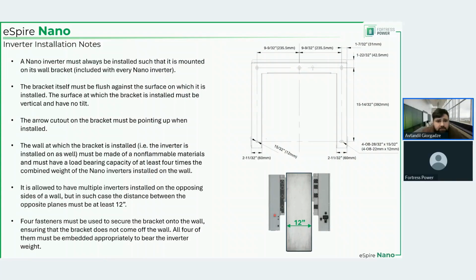The wall which you use to mount the inverter must be non-flammable. That is addressed by default when we're talking about the battery cabinet because it's made of steel, so it's non-flammable. But installing this on a wooden wall or something like that would not be acceptable. Also, there should be no incline. If you take your level, the surface on which you're attaching this bracket should be perfectly vertical.